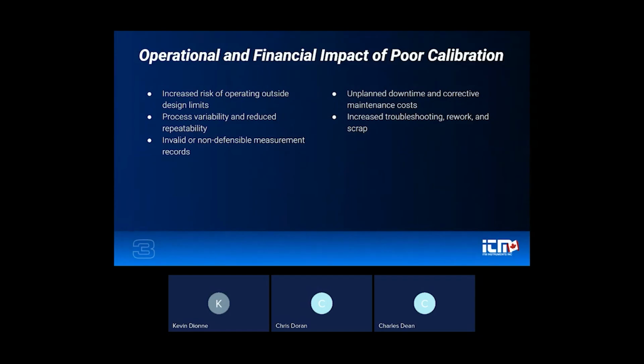much broader. So from an operational standpoint, inaccurate pressure measurements can cause systems to operate outside of their intended design limits without triggering any alarms. Even if those deviations seem relatively small, they increase mechanical stress on your components, such as pumps, regulators, valves, and it can shorten your equipment's life cycle and increase your maintenance frequency.